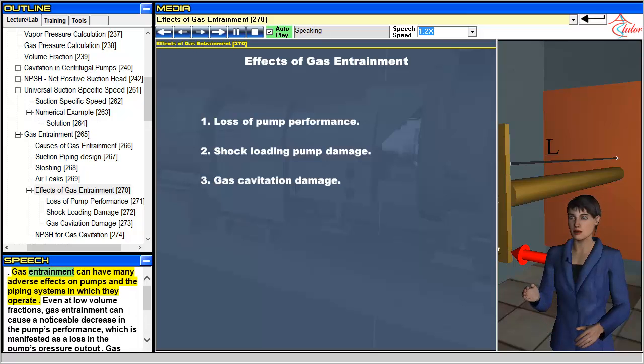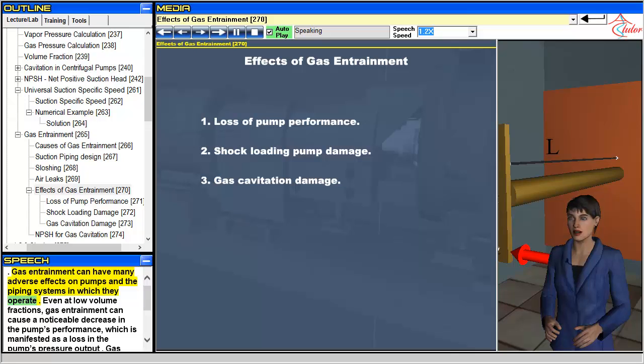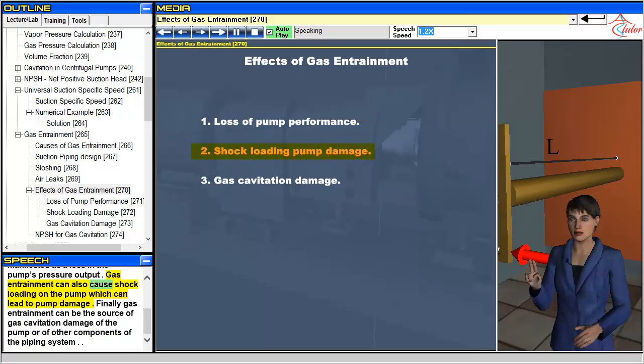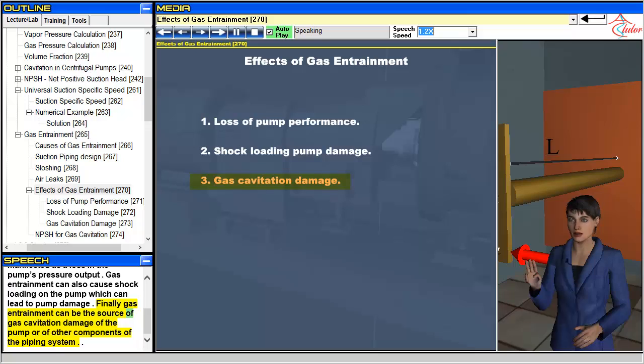Gas entrainment can have many adverse effects on pumps and the piping systems in which they operate. Even at low-volume fractions, gas entrainment can cause a noticeable decrease in the pump's performance, which is manifested as a loss in the pump's pressure output. Gas entrainment can also cause shock loading on the pump which can lead to pump damage. Finally, gas entrainment can be the source of gas cavitation damage of the pump or of other components of the piping system.